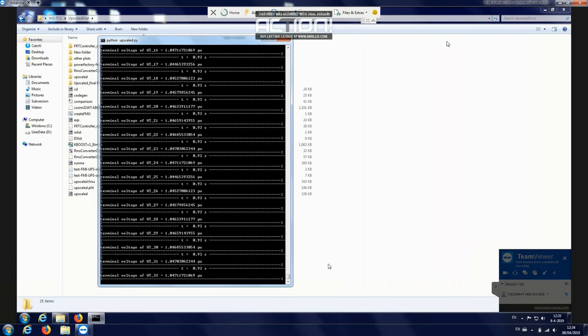Now, if you look closely at the screen, at 1 second there would be a short circuit and the voltage will go down. As you can see, the voltage has gone down across all the wind turbines, showing that the fault has happened, and our controllers will come into effect. With the boosting of the reactive current, voltage support will be provided. This fault ride-through support is critical because it is a necessity for grid code compliance.